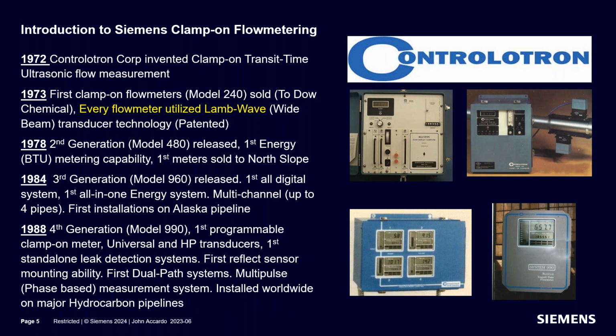We had a meter that we could now program. We had high-end systems such as standalone leak detection systems. We introduced reflect transducer mounting. We had our first dual path systems, and we used a phase-based measurement system using a multi-pulse transmit for the first time. Prior to that, we used more or less a single pulse transmit.